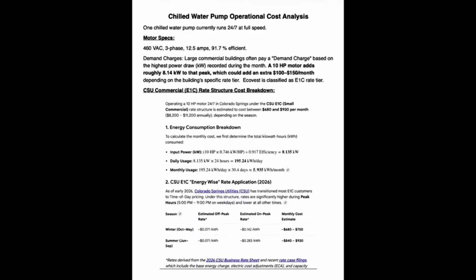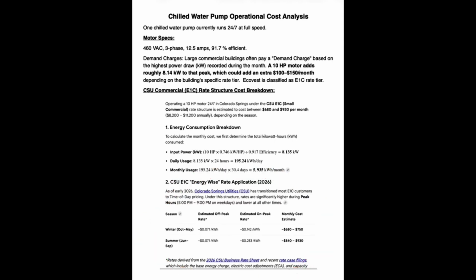So I did a chilled water pump operational cost analysis that you see here. To run one chilled water pump 24 hours a day, 7 days a week, you can see the motor specs here: 460 volt, 3-phase, 12.5 amps, and these are 10 horsepower chilled water pumps. Operating that 24/7 here in Colorado with our rate structure, it's costing us between $680 and $900 a month. That's $8,000 to $11,000 a year just to run this one chilled water pump. That's a lot of money.